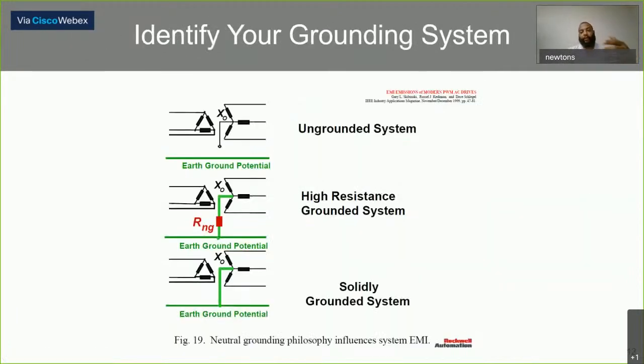So after you determine your grounded system, you'll need to take a look at your power jumpers. All drives, whether it's Rockwell or a third-party VFD, are going to come with a set of power jumpers, and you need to apply the jumpers appropriately per the manual based on the grounded system that you have. If you have a solidly grounded system with PowerFlex drives, you will insert one or both, depending on how many jumpers they have, into the drive. If you don't have a solidly grounded system, you remove one or both, depending on the number of jumpers that you have, out of that system. So to recap, identify your grounded system and apply your power jumpers appropriately.